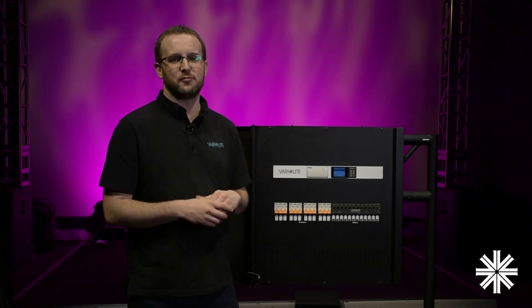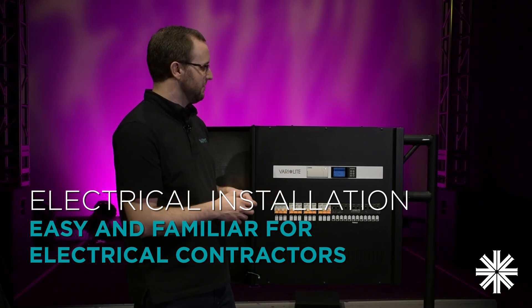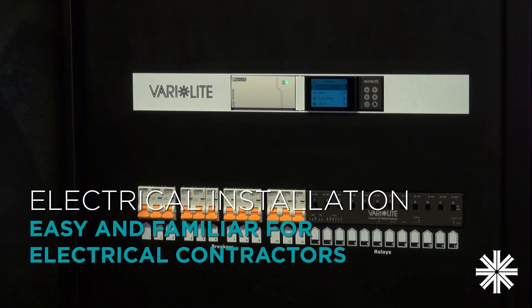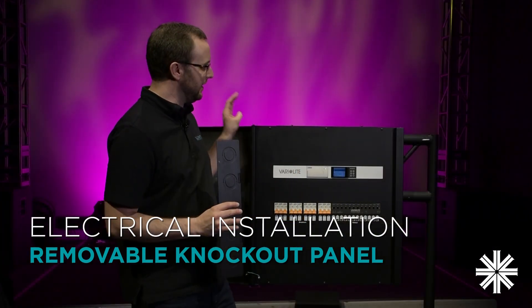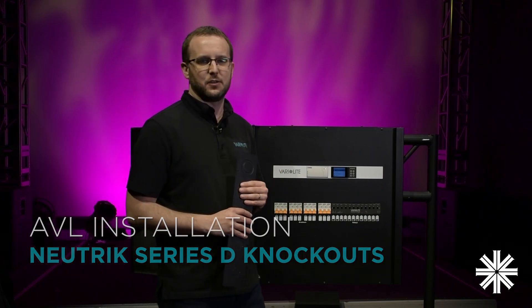We've made the robust enclosure of Rig Switch Plus really quick, easy, and familiar to install. The door and the front panel can be removed, revealing a wiring chamber along the top that will be very familiar to electrical installers. The plate on the top here includes a range of knockouts, or alternatively you can remove it completely if you plan to have trunking running along the top of Rig Switch Plus. Along the edges and the bottom, we have Neutrik Series D knockouts, so if you want to put maybe an XLR or an EtherCon connector, there are positions ready for you to do that.